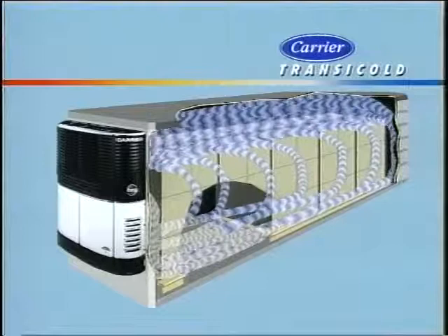The switch moves from side to side. Toward the trailer is the glow position, and away from the trailer is crank. Hold the switch in the glow position, then turn the start run off switch to the start run position to preheat the engine. When the display powers up, "Manual start mode selected" appears in the message center. The colder the engine is, the longer you will have to glow it. However, you never have to preheat the engine for more than 45 seconds. When the engine is preheated, place the manual glow crank switch into the crank position until the engine starts.